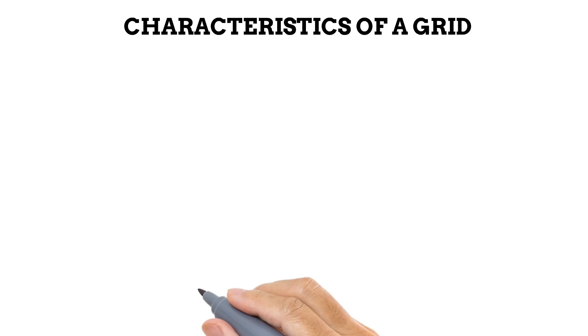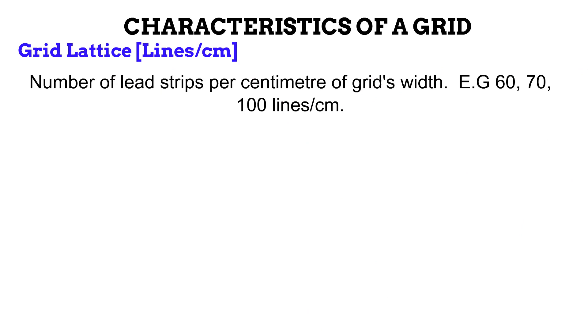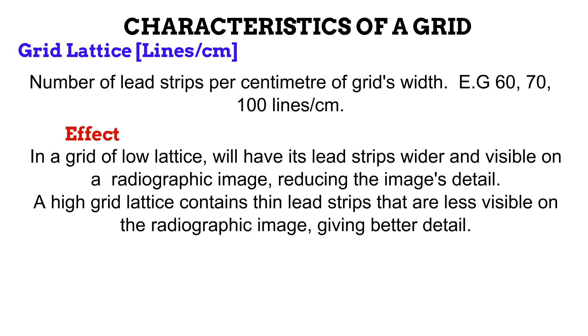Next is the grid lattice or grid frequency, measured in lines per centimeter or lines per inch. The grid lattice is the number of lead strips present in each centimeter of the grid's width. You can have a grid lattice of 60 lines per centimeter, implying 60 lead strips per centimeter, and some are as high as 100 lines per centimeter. A grid of low lattice — that is, a grid with fewer lead strips — produces an image with reduced recorded detail, because low lattice grids usually have wider lead strips, which are more visible on a radiographic image.